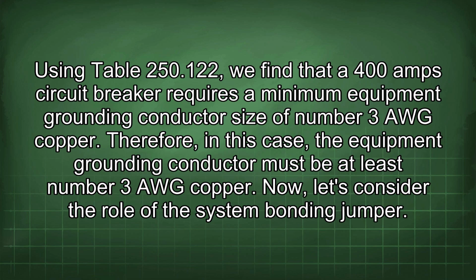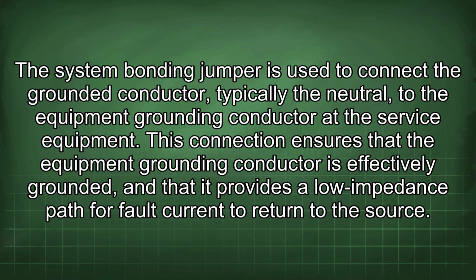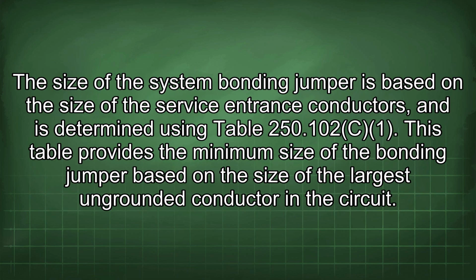Now let's consider the role of the system bonding jumper. The system bonding jumper is used to connect the grounded conductor, typically the neutral, to the equipment grounding conductor at the service equipment. This connection ensures that the equipment grounding conductor is effectively grounded and that it provides a low impedance path for fault current to return to the source. The size of the system bonding jumper is based on the size of the service entrance conductors and is determined using table 250.102(C). This table provides the minimum size of the bonding jumper based on the size of the largest ungrounded conductor in the circuit.